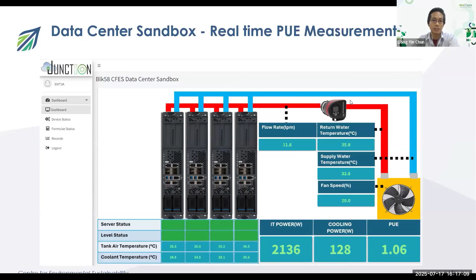For the 4 servers running here, we send the cooling water to a fan that's outside, and we just control the fan. You can see the fan speed running is just 20%, and the PUE is 1.06. We have the cooling water going back to the server to take out the heat from the coolant. So for this particular example, we don't need any chiller, we don't need any cooling tower — it's just a dry cooler, a fan to cool down the cooling water, and it can just keep running continuously. That's all for my technology.